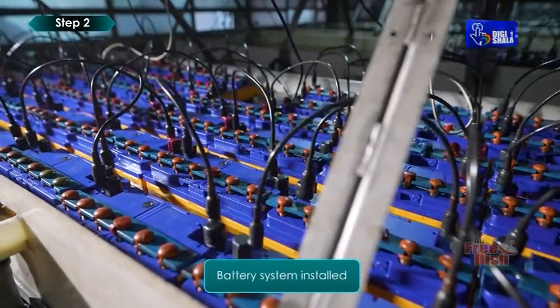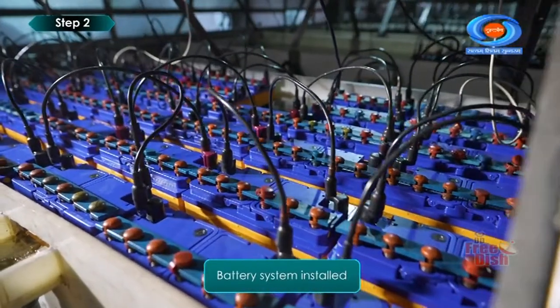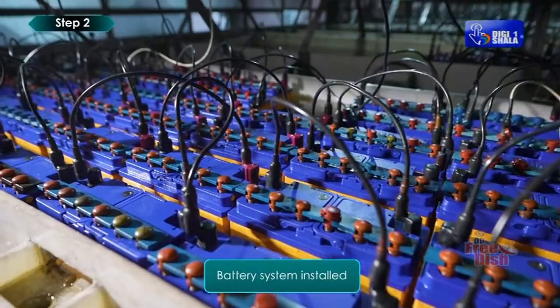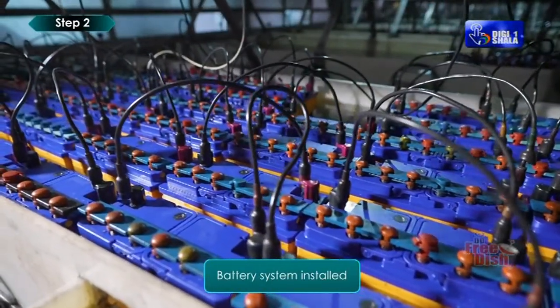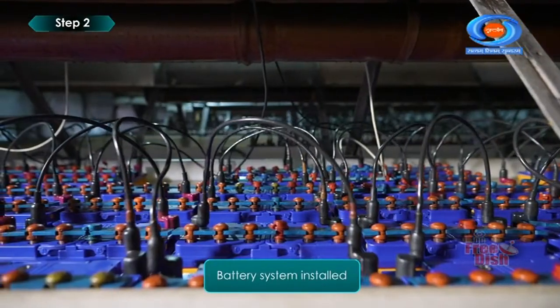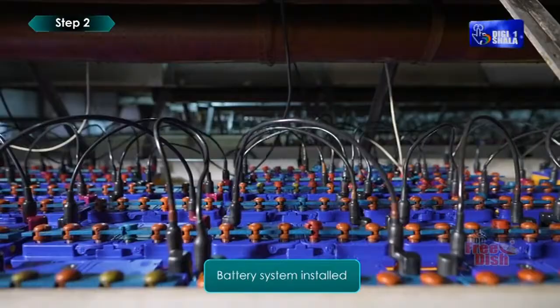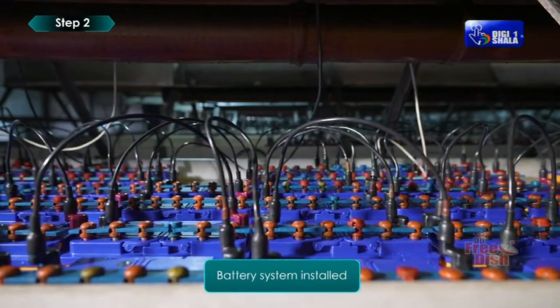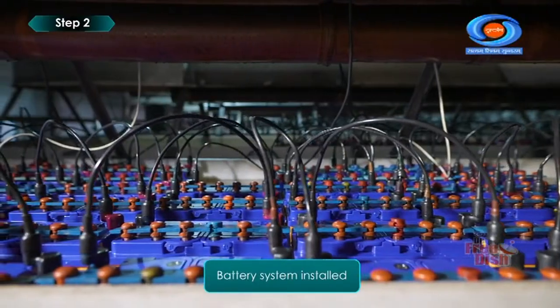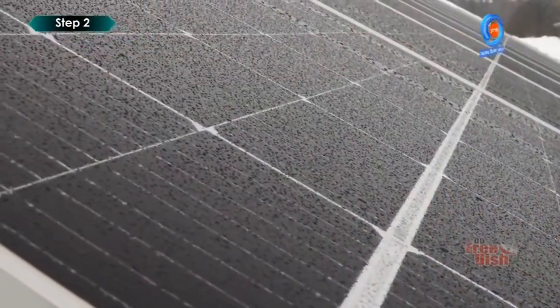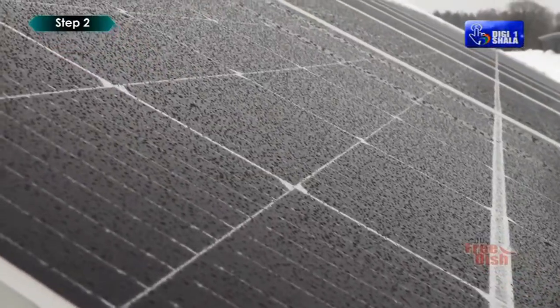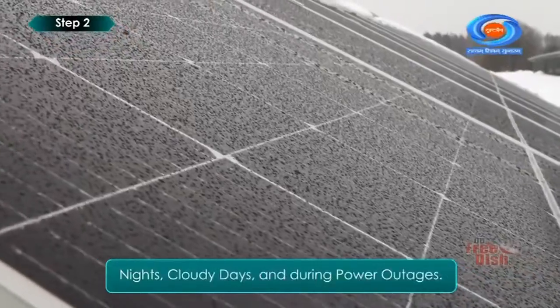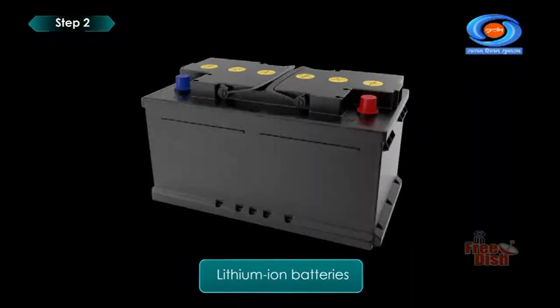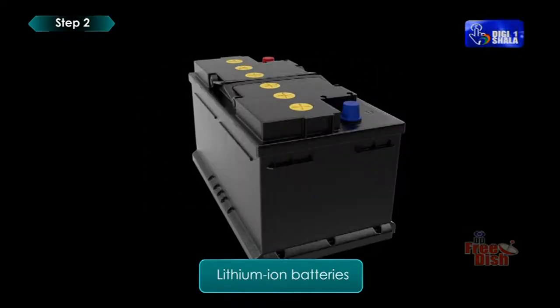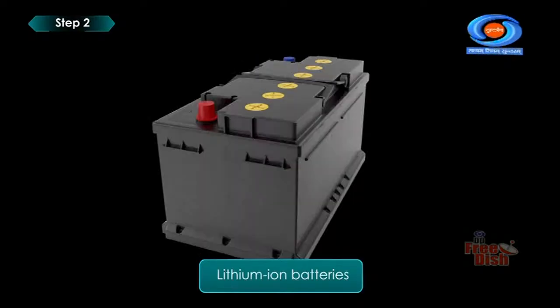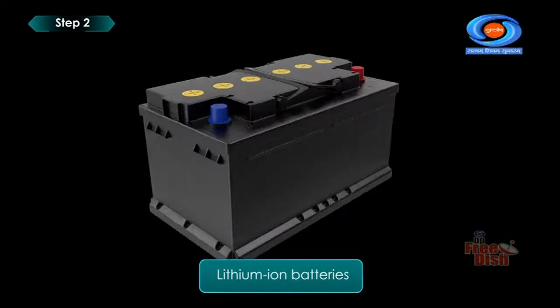Battery system installed. A battery is used in a solar system to store the excess electricity generated by solar panels. Solar panels can be connected directly to the load, but the solar output may not be constant, high during the day and low at night. So the high power generated during the day is stored in batteries and may be used during the night. You can then use that stored energy at times when your solar panels don't generate enough electricity, including nights, cloudy days, and during power outages. Solar panel companies prefer lithium-ion batteries because they can store more energy, hold that energy longer than other batteries, and have a higher depth of discharge.